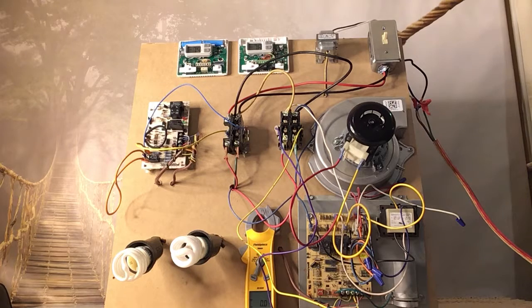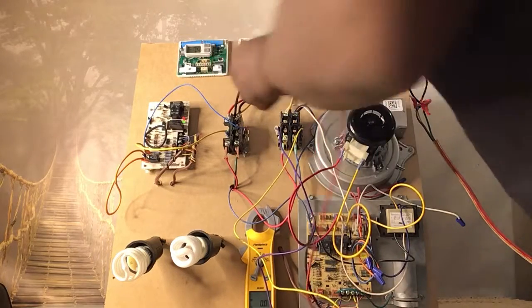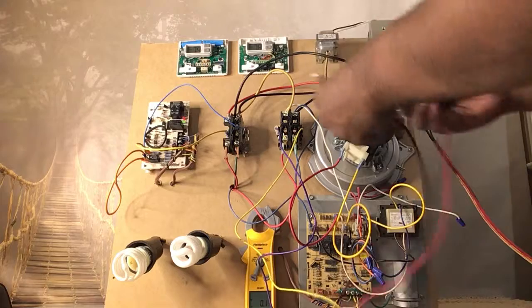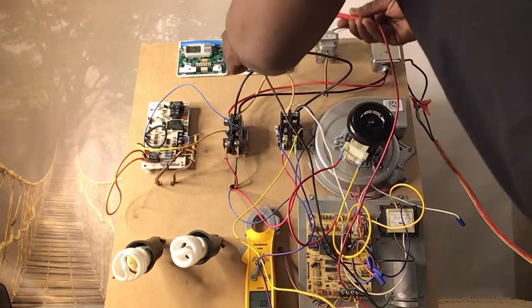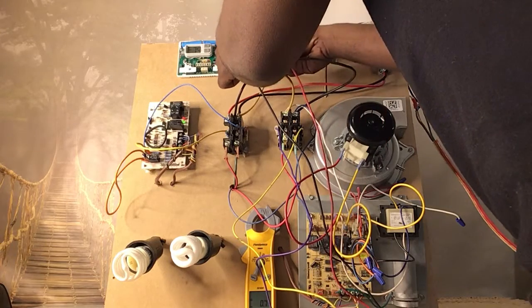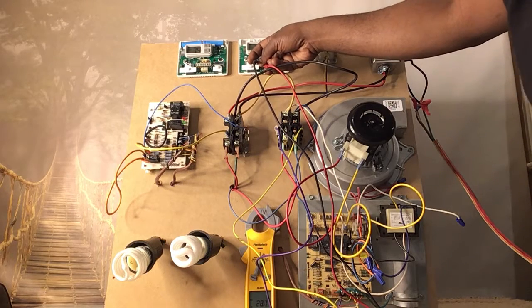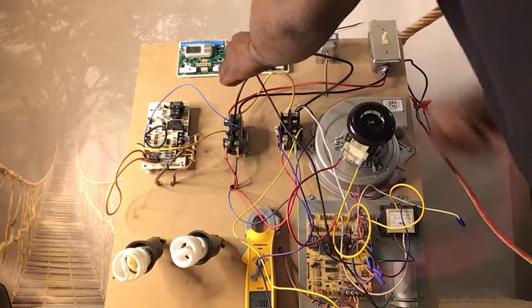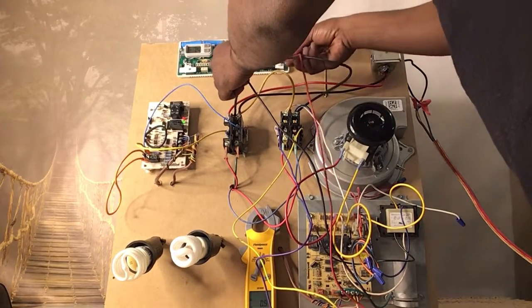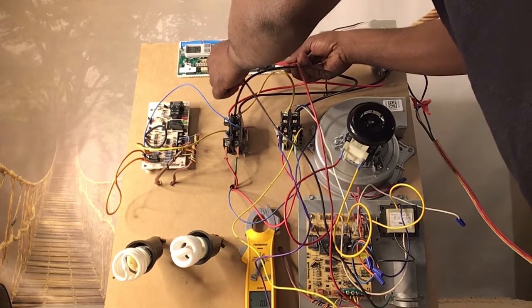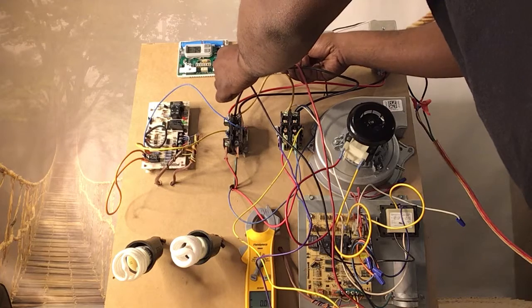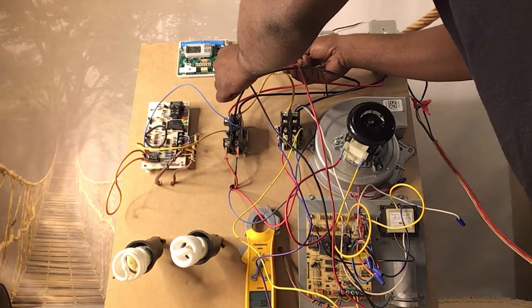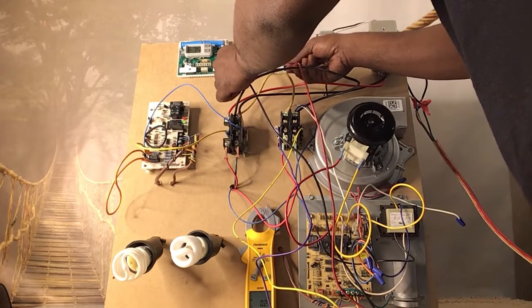So what your thermostat is actually doing, so when you go to your thermostat and you check from common to red, or common to your 24 volt side, you should have 24 volts. So I'm gonna go from C to R, and I don't know if y'all can see that, but that's reading 28 volts, right? So what happens is that common is like a ground. It remains the same. So if you check common to any other wire, you wouldn't get nothing. But if you check red to any other wire, you would get 24 volts. Okay? So what your thermostat ultimately does is that it jumps power from one side to another.